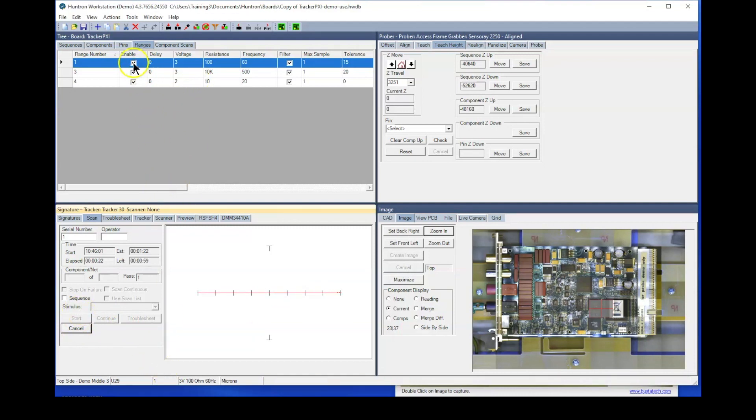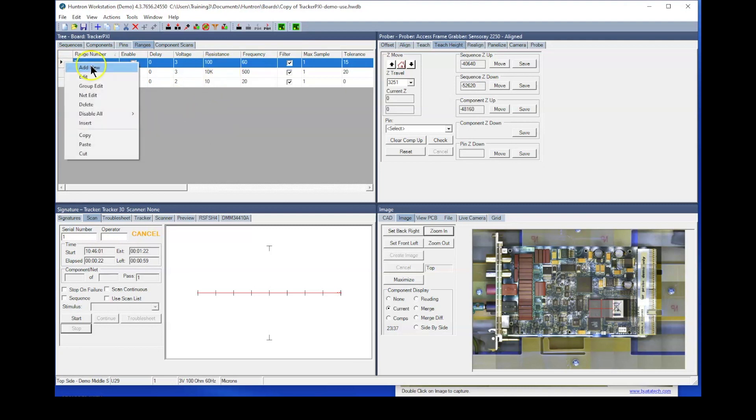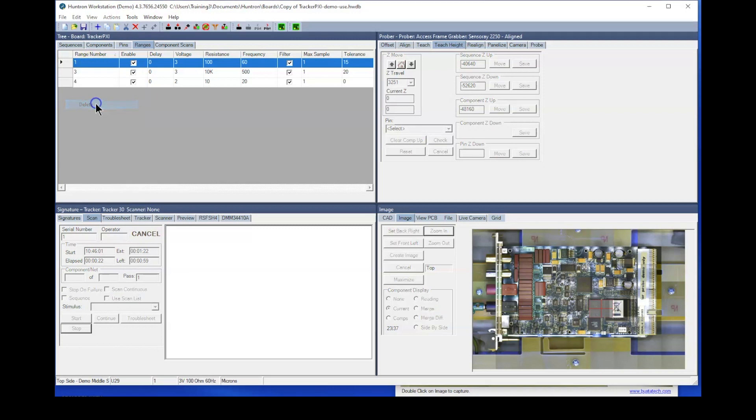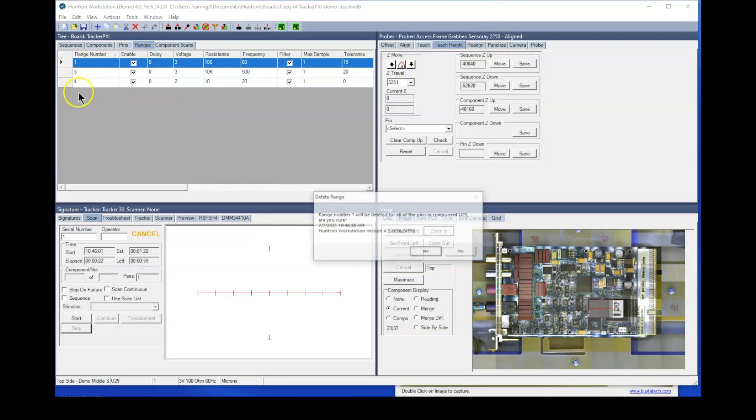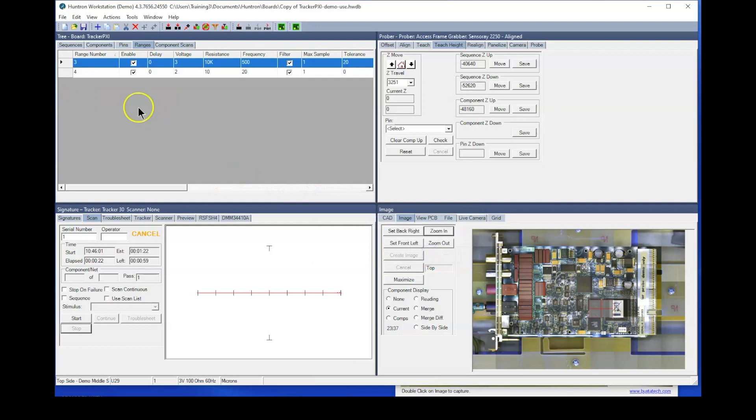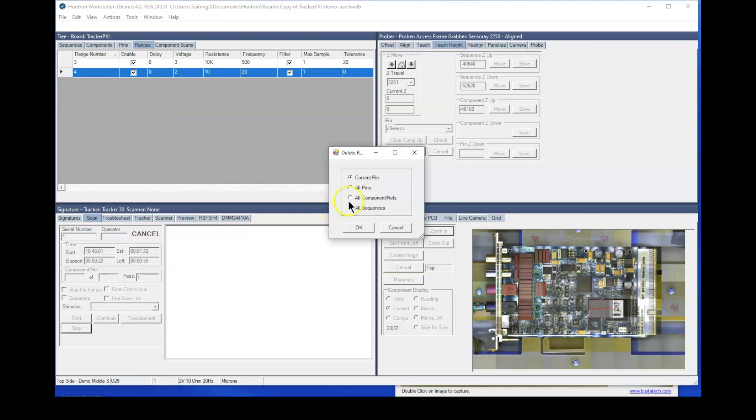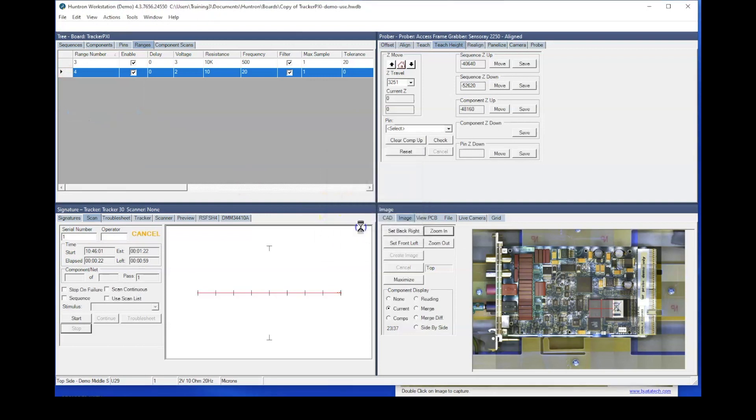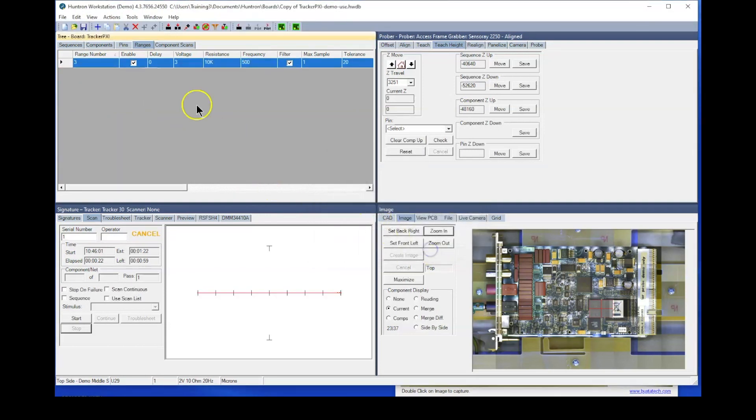So now let's go and disable. Well, actually, what I'm going to do here is delete two of the ranges. I generally don't want to test ICs in anything other than 10k ohm range. And so we'll just go ahead and delete this first one. Delete. We'll delete for all pins. And then we'll also delete this other 10 ohm range. Select, delete. All pins. So now we have just one range on this.